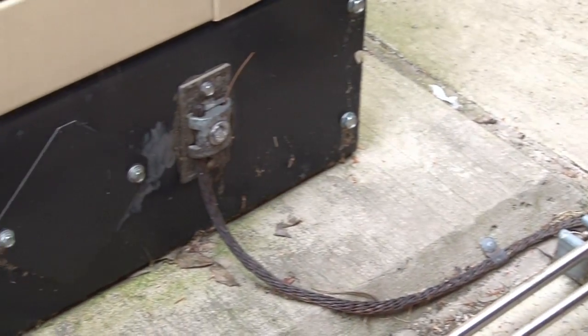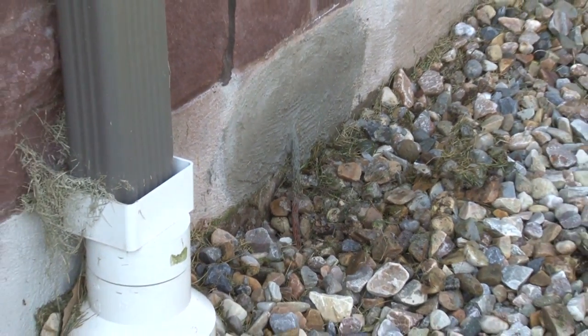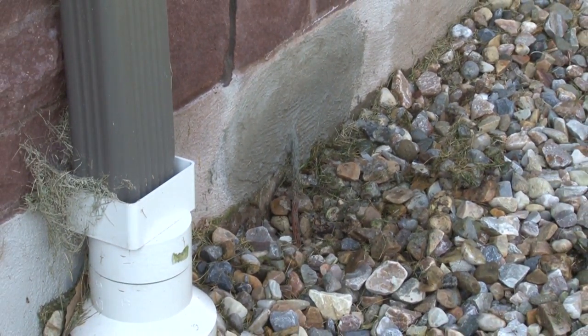The generator outside is bonded. The compressors that we come within six feet of are all bonded. Any structural steel members would be bonded. Door tracks, if they have a remote path to ground, and downspouts, if the downspouts went into a metal pipe in the ground, would be bonded as well.